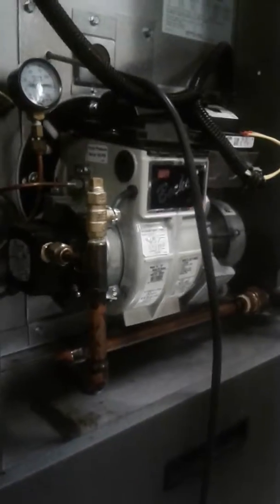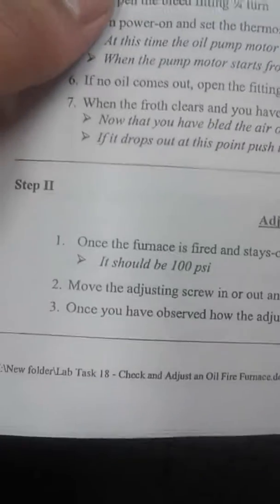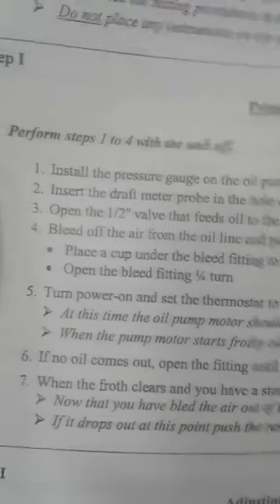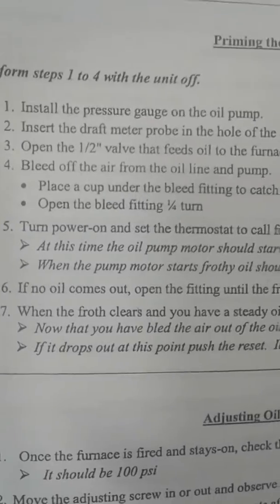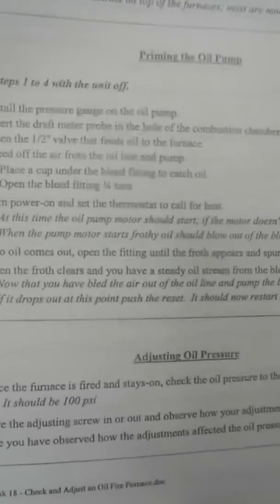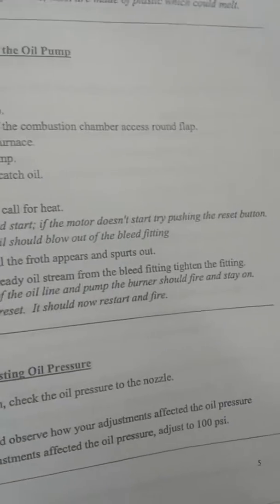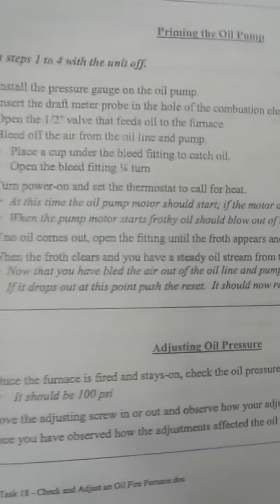Okay, now, let's see here. It says, open the bleed fit. Okay, ready to do that. Turn power on. At this time, the oil pump will start. Motor should start. If the motor doesn't start, try pushing the reset button. When the pump motor starts, frothy oil should blow out through the bleed fitting. We had pretty much a steady stream, so we didn't really see too much of it, okay?